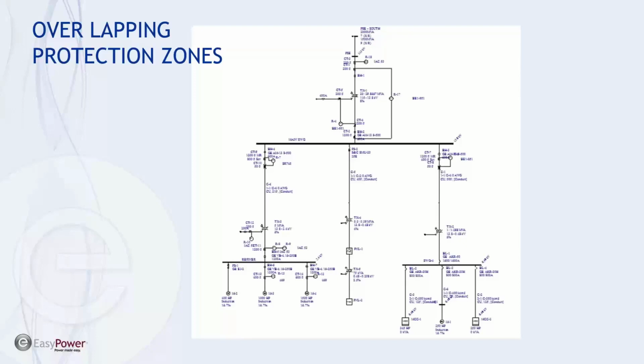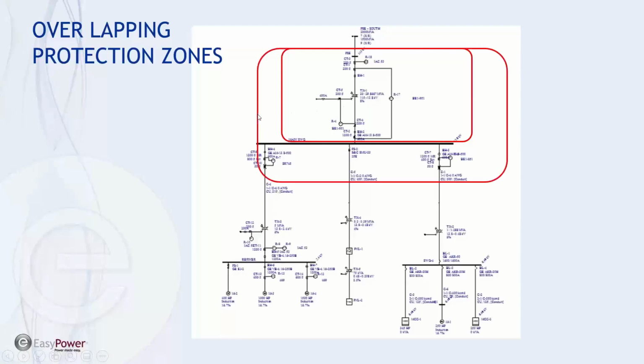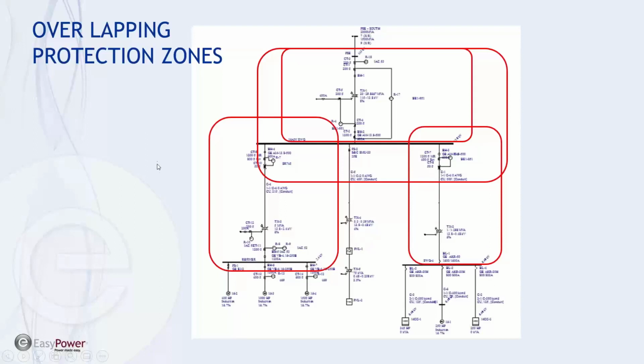Something that is important is understanding the need to have overlapping zones. For instance, the first example we're going to do is going to set up the zone for main transformer protection. And once we've got that dialed in, then we want to have an overlapping region that includes the next level of protective devices and make sure they're coordinated with the downstream protection on the transformer. And then the subsequent feeders, likewise, are coordinated with the upstream, with the overlapping element, and that will ensure protection for the whole system. So one of the things that I'm going to try to emphasize is if you follow this policy and coordinate on the largest downstream load, then the rest of the loads or the rest of the feeders in that particular bus will be covered. And it's a question that comes up, and sometimes it's worth being able to prove that to yourself.